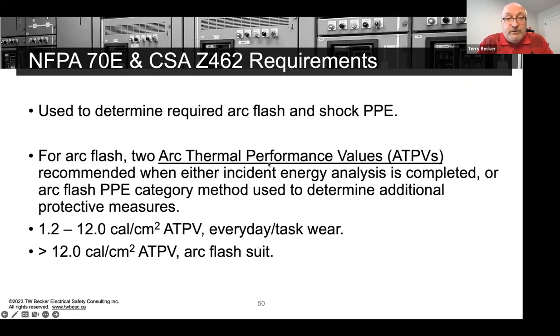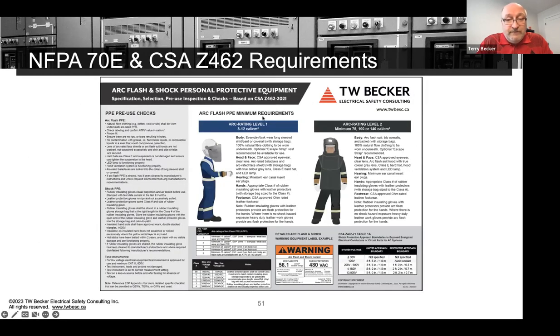All right. So what we're determining is arc flash PPE with an arc thermal performance value, not an HRC2 or a category number or a level A, B, C, D, E. That's completely wrong, right? Arc rated clothing is specified, ordered by the employer with an arc thermal performance value. And the worker identifies the arc thermal performance value they need. And there's two arc rated levels defined in 70E and Z462, 1.2 to 12 cal, everyday task wear, or greater than 12, which would be an arc flash suit. All right. So this is another infographic where I show you an image, right, of everyday task wear, coverall, shield and balaclava versus an arc flash suit and two arc rated clothing levels. Full body protection, top of your head to your fingertips to your toes when you're exposed to arc flash.